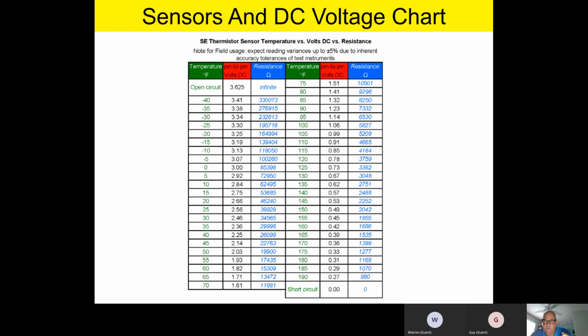If I took that sensor off the board and ohmed it out, it should be 85,398 ohms, with the sensor just with the harness in your hand. You unplug the sensor and ohm it out. So that's the basic check you're going to do. You measure the temperature the sensor is subject to. You then take your needlepoint meter leads and read the DC voltage on that sensor with it plugged in, the pin-to-pin voltage. And then you unplug the sensor from the board and ohm it out to see if the ohms is close to chart value.